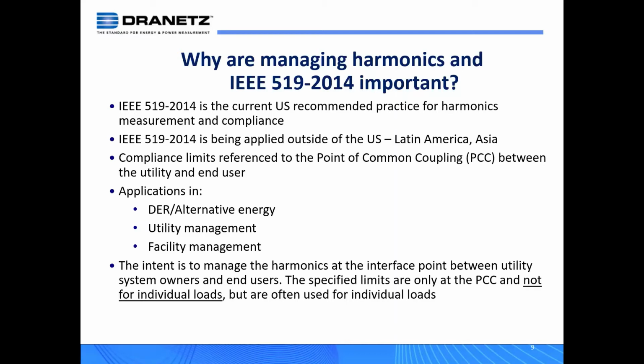Well, just in summary, the compliance limits are referenced at the point of common coupling between the utility and the end user. I'll skip over the applications for a second, but the intent is to manage the harmonics at the interface point between the utility and the system owner and the end users. So this is that point of common coupling. The specified limits are only at the point of common coupling, but they're not really intended for individual loads. They're often used that way, but this is meant to manage the relationship between the provider of electricity, the utility or the system owner, and the end user, at that point of common coupling.